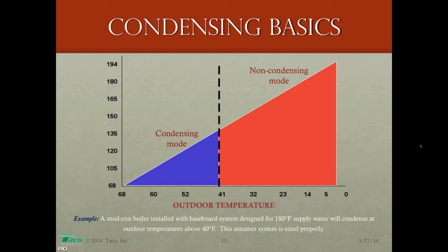Well, yeah, they're different schools of thought. Anthony sent me these slides, and I'd like to share them with you. And Anthony, just send me a note if I get anything wrong here. This is if we set up an appropriate outdoor reset curve, what you have here is a temperature curve for this particular boiler, a ModCon boiler installed with a baseboard system designed for 180-degree supply water temperature on the coldest day of the year.